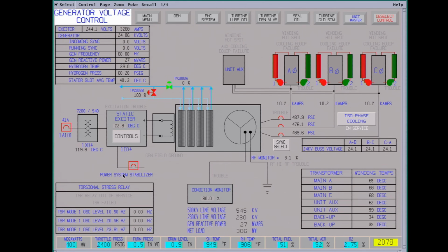We have a power system stabilizer. This has to be in service. I think it comes in about 60 megawatts. This runs the exciter and tries to take out any kind of swinging in the grid. Basically stabilizes the power.